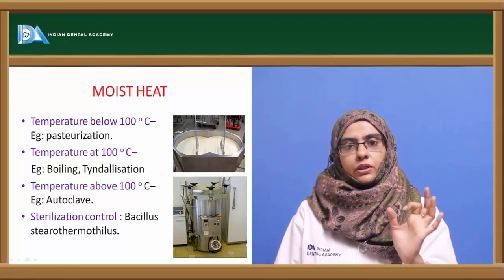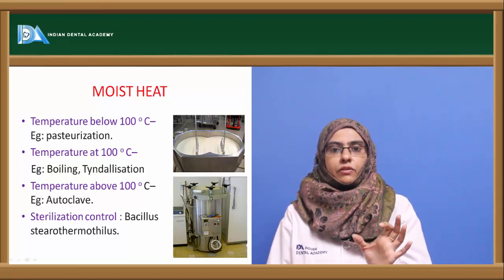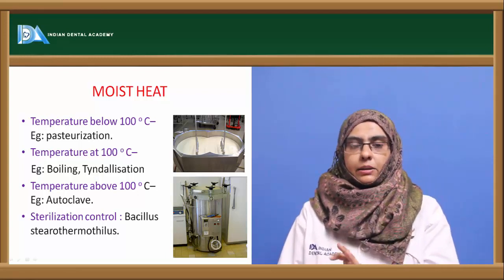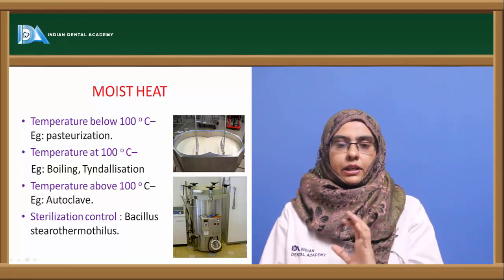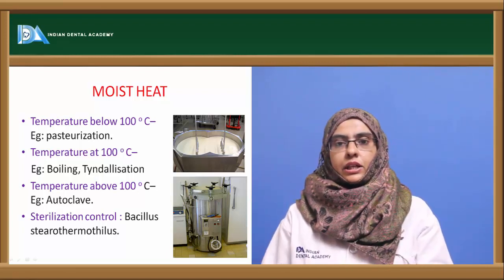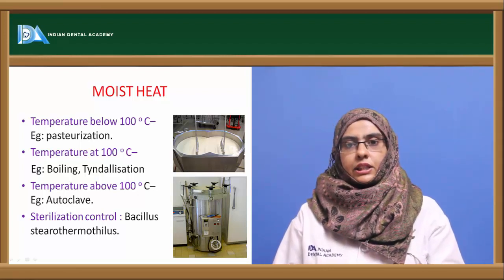So you have to hold this particular 120 degrees centigrade for around 15 to 20 minutes. That is called the holding time. At this time you are eliminating most of the organisms.